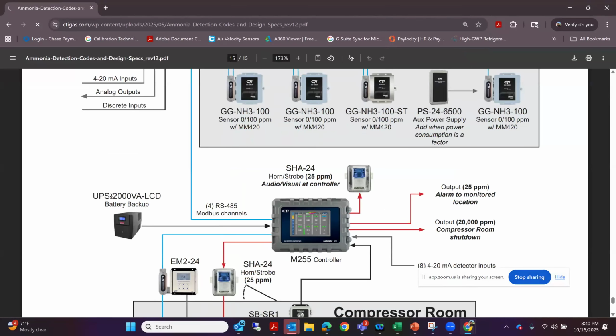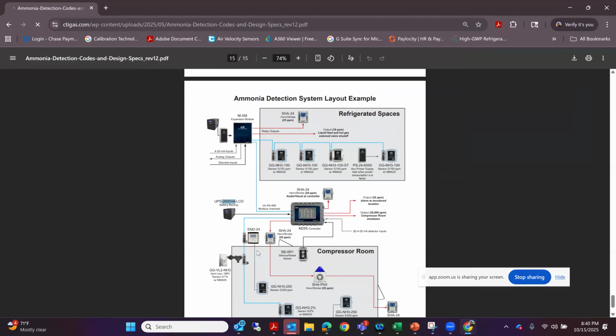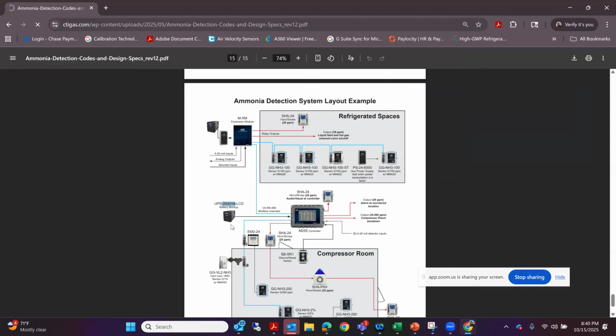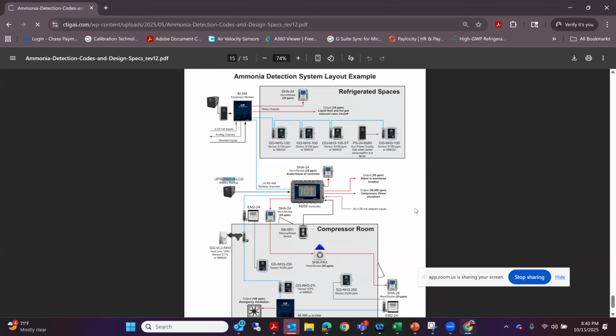So we put a 2000 VA system on this, and really, if you're looking at this drawing, with everything that is running right here, just on this drawing alone, we're going to be able to stay up for several hours, maybe even half a day, or most of the day maybe, and the leak would more likely be mitigated. But as far as trying to keep up a huge system where we've got 100 of these horn strobes out there and 25 to 35 sensors out there, you're talking a lot of money, and you're talking about a whole wall of rack-mounted UPS batteries set up to do that.